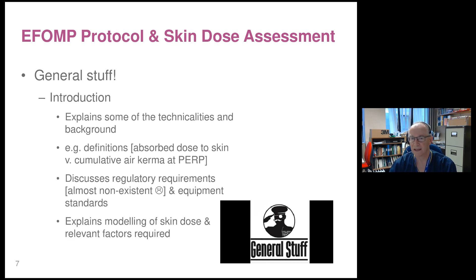So coming on to the standards, the equipment standards that we all have to live with because they're international standards. The current version of the interventional X-ray equipment standard, which is that top one, IEC 60601-2-43, says it should have a dose map. And it says we prefer a skin dose map where possible, where skin dose is the absorbed dose to skin. So much more relevant to how a patient is going to react to that radiation.